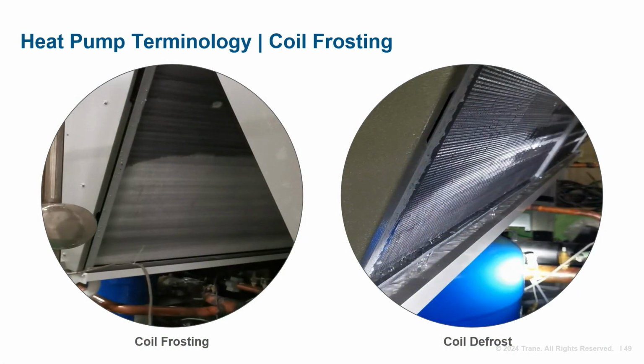Shown in the attached image on the left is an example of a coil frosting. Conditions that would accumulate additional frost would be a 50-degree dry bulb with a 48-degree wet bulb. At these ambient conditions, the logic allows defrosting when the outdoor coil reaches its permissible threshold of 32 degrees. As frost begins forming on the face of the coil, the heat transfer process becomes less effective. This is when the coil defrost mode switches the flow of refrigerant, utilizing the heat of compression from the cooling cycle, thus thawing out the outdoor coil and removing any remaining frost as shown in the right-hand image.